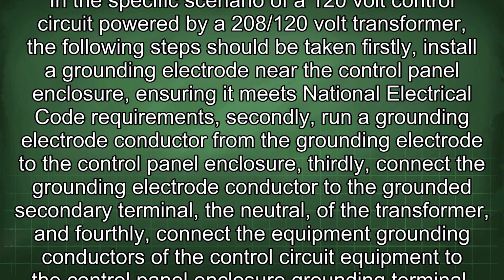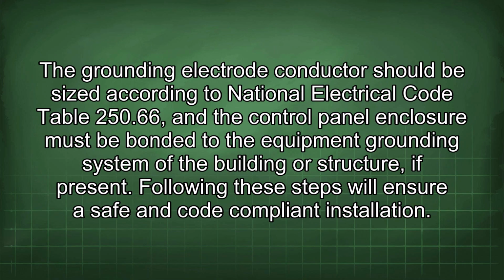And fourthly, connect the equipment grounding conductors of the control circuit equipment to the control panel enclosure grounding terminal. The grounding electrode conductor should be sized according to National Electrical Code Table 250.66, and the control panel enclosure must be bonded to the equipment grounding system of the building or structure, if present. Following these steps will ensure a safe and code-compliant installation.